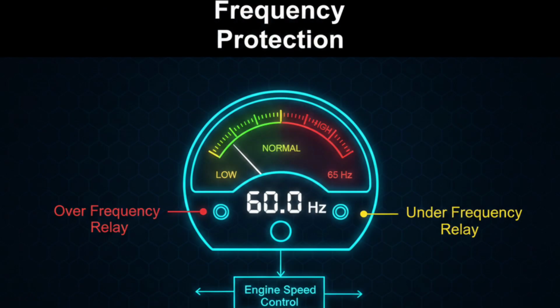Under frequency or over frequency protection. Frequency directly depends on engine speed. If engine speed increases, frequency rises. If engine speed decreases, frequency drops. Low frequency can cause motor overheating and poor performance. High frequency can damage sensitive electronics and navigation equipment. Frequency relay monitors system frequency continuously. If frequency crosses safe limit, protection relay sends trip signal. Maintaining stable frequency is very important during load changes. Governor tuning plays a major role in frequency stability.